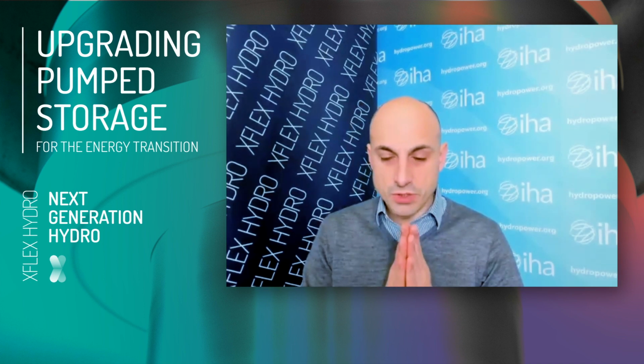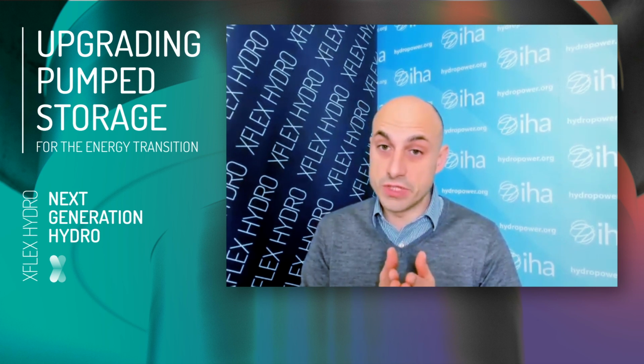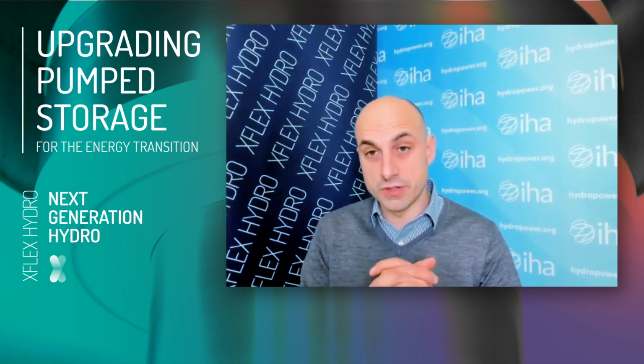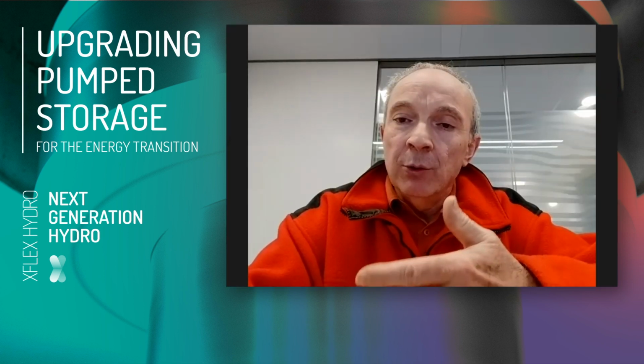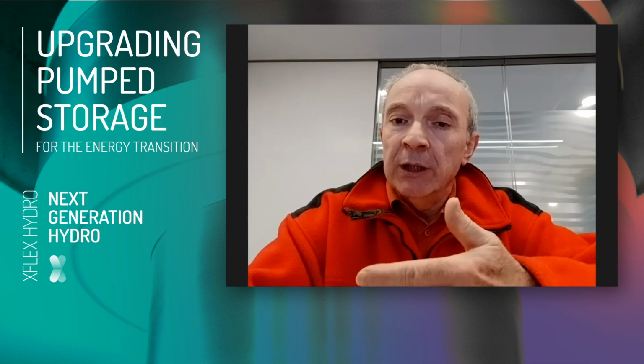Can I ask you to elaborate a bit more on what type of services Grand Maison is capable of providing to the grid operating in hydraulic short circuit? It is now possible to add 2 important services for the grid: the primary reserve, or so-called FCR, frequency containment reserve, and also automatic frequency restoration reserve, or secondary reserve, for grid frequency support. So now these 2 grid frequency ancillary services are available with the units and with the scheme being in overall pumping mode.